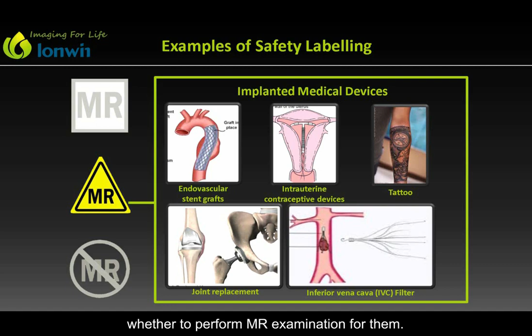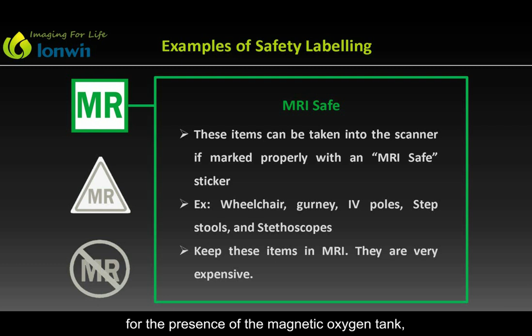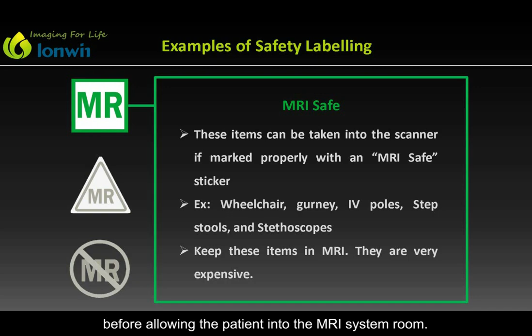Also, there are some items that can be taken into the scanner room if marked properly with an MRI safe sticker. For example, if you're assisting a non-ambulatory patient into the MRI system room, make sure the patient is using a non-magnetic wheelchair or is on a non-magnetic gurney. Inspect the wheelchair or gurney for the presence of a magnetic oxygen tank, IV pole, or similar components or accessories before allowing the patient into the MRI system room. Fortunately, there are many commercially available devices, including wheelchairs, gurneys, IV poles, oxygen tanks, and maintenance equipment, that are made from non-magnetic or non-metallic materials that may all be used safely in the MRI environment.